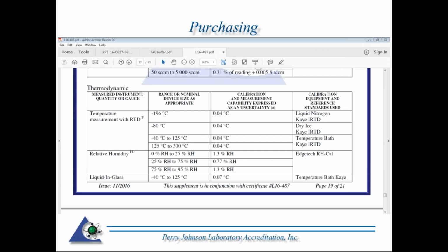Again, in this particular example, you're utilizing a 17025 provider. You want to ensure when you're making this purchase, if that is a requirement, that just because they're 17025 accredited does not mean it's going to be under their scope of accreditation. Here's an example of a scope that includes thermodynamics and relative humidity, in which the lab provided those reports to you, and they were done on an accredited type report. This is a clear indication that they are accredited to do that particular calibration. So these are items that, for calibration, particularly if you're looking for traceability and 17025 accreditation, would need to be reviewed.